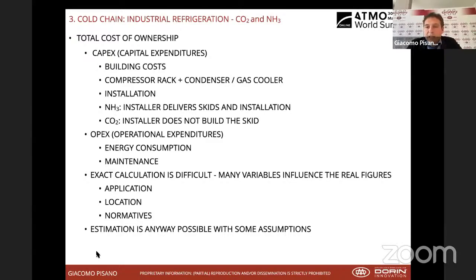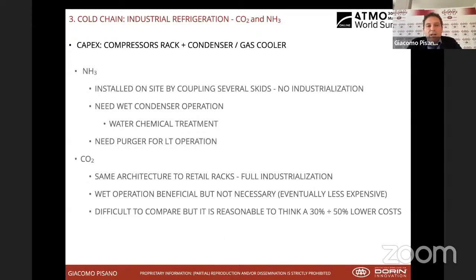Clearly, an exact calculation is very difficult to make when we do a total cost of ownership comparison between CO2 and ammonia, but some kind of estimation is possible with some sort of assumptions. Which are these assumptions? Basically, when we talk about the rack and the condenser, in case of ammonia, the ammonia skids are normally installed on site. There is really no industrialization in building those skids. They normally need a cooling water or an adiabatic cooling tower or an adiabatic cooling, which means water chemical treatment is needed. When you are using ammonia for low temperature operation, you will definitely need a purger.